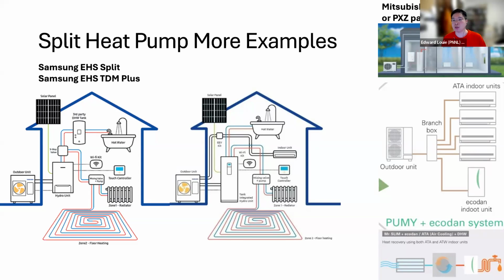On the right-hand side, Mitsubishi has a few different lines, Mr. Slim, PUMY, PXZ. Those lines can all be paired with EcoDan, which is their name for a refrigerant to water heat exchanger. And in these graphics, you can see that you can have either multiple indoor units that are connected via refrigerant, or just one indoor unit that is more of a central refrigerant to air heat exchanger or air handler, and then the other branch being domestic hot water. Next slide.